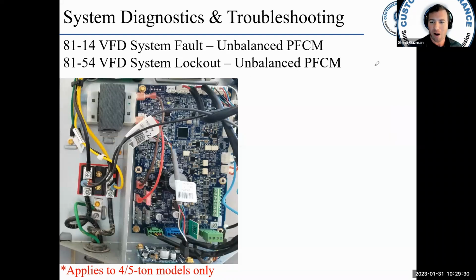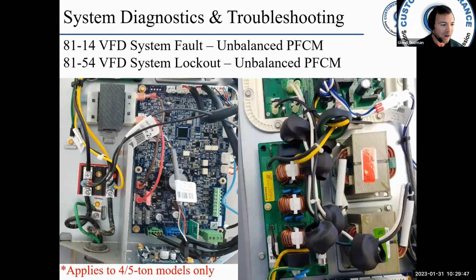8114, unbalanced power factor correction monitoring, and 8154, VFD system lockout, unbalanced PFCM. Okay. Kind of the same thing here. Most likely caused by a disconnected or faulty reactor. The VFD will shut down and attempt to restart. After 2 occurrences within 10 minutes, you get the 8154 and it is locked out for 4 hours. Okay, check your reactors, disconnect, measure the resistance of both. It should be a low resistance. If it's open, replace the reactor. If it's a low resistance, you've checked all your connections, there's no signs of overheating, everything else looks fine, then you'll have to replace the VFD.